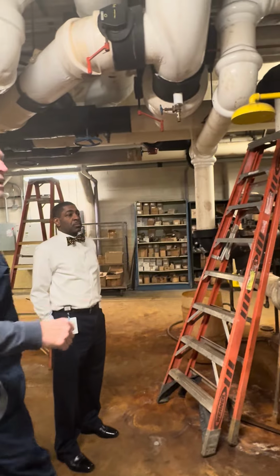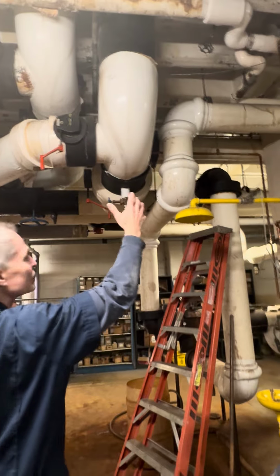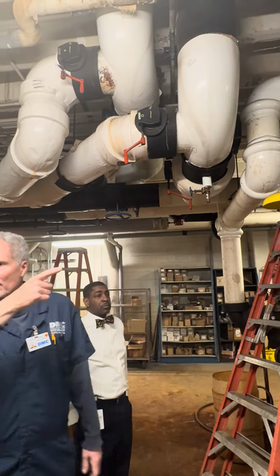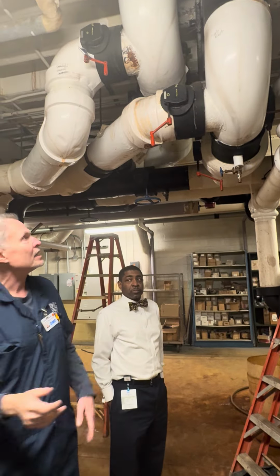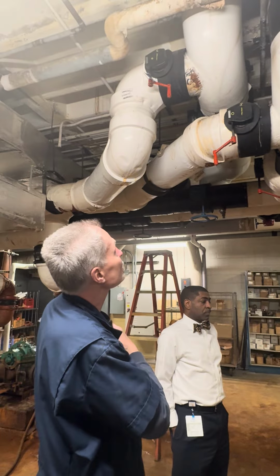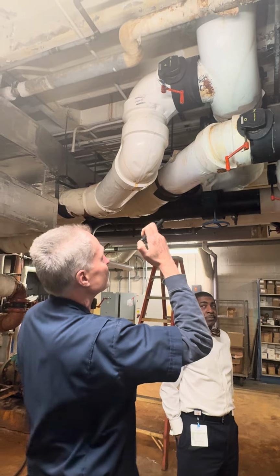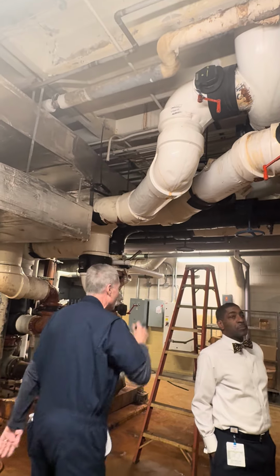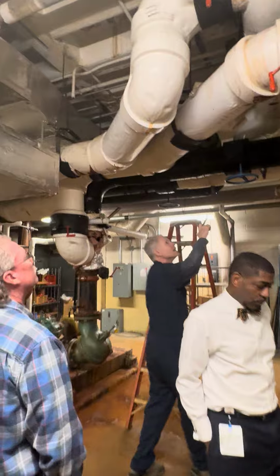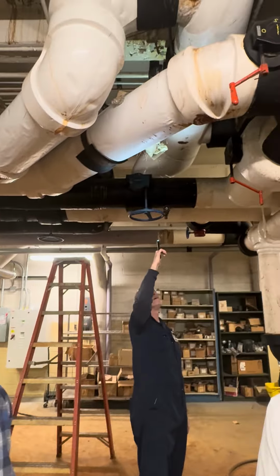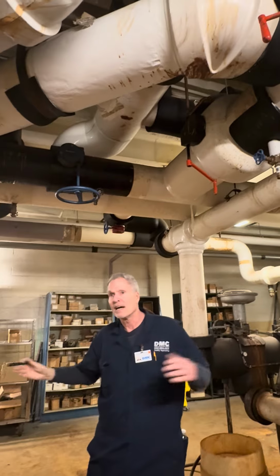But anyway, after you come in and open up those valves in the south building, I showed how you split it. Now this building's isolated, marked east addition, so that's coming around. You open that valve halfway, and you open that valve up here halfway. Feed in there, and that goes to both of these two air handlers.